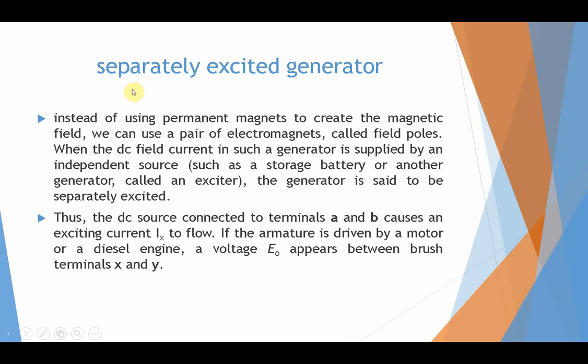There are a few types of DC generators, two of which are the most common. One is the separately excited generator, and the other is not separately excited, meaning it does not require an external DC source. In a separately excited generator, instead of using a permanent magnet to create the magnetic field, we use a pair of electromagnets called field poles. When the DC field current is supplied by an independent source such as a storage battery or another generator called an exciter, the generator is said to be a separately excited generator.